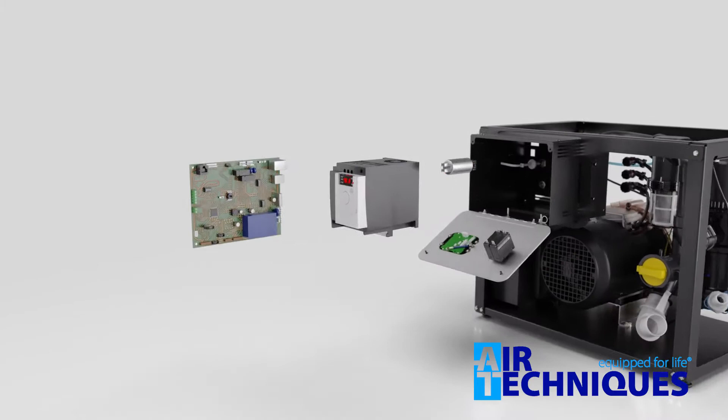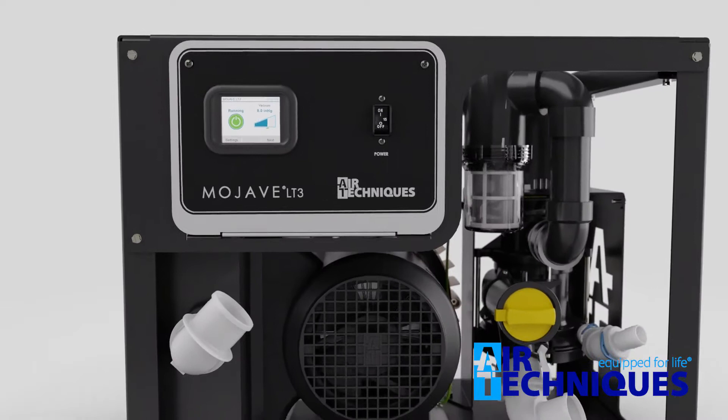The air pump spins really fast — it's very powerful and maintains a negative pressure at longer air flows. So the doctor has more negative pressure when working on patients. It also has a lot of really cool features; for example, it works on a variable frequency drive, like its older brother the Mojave Classic systems.